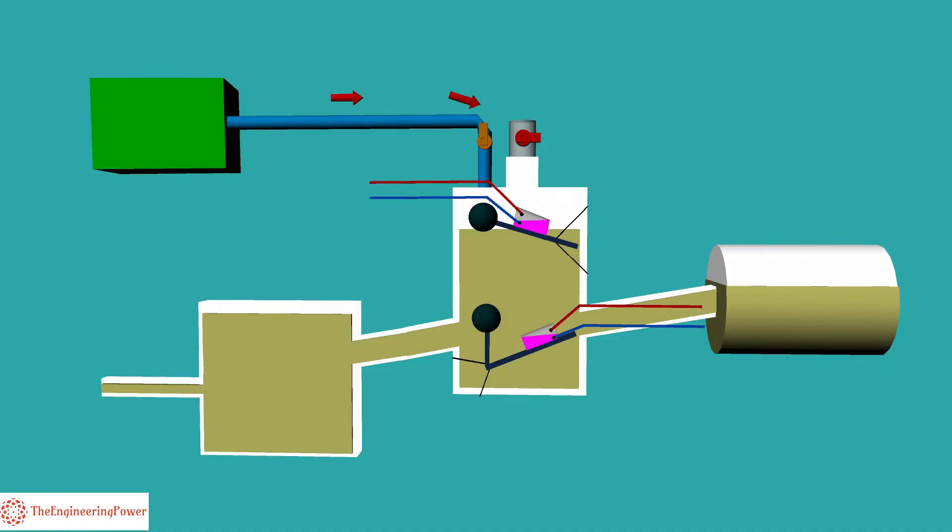Relay is pressurized with an air pump and the gas pressure is noted on the gauge at which the alarm of the Buchholz relay operates. The volume of the gas required to initiate alarm can be adjusted by adjusting the micro switch of the Buchholz relay.